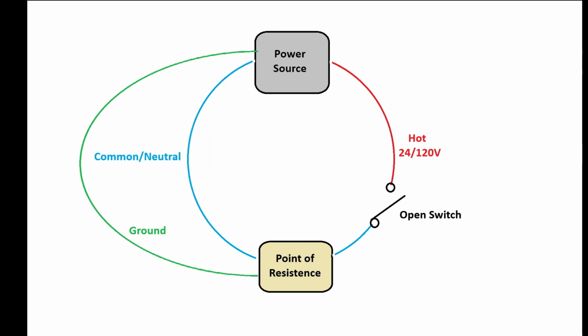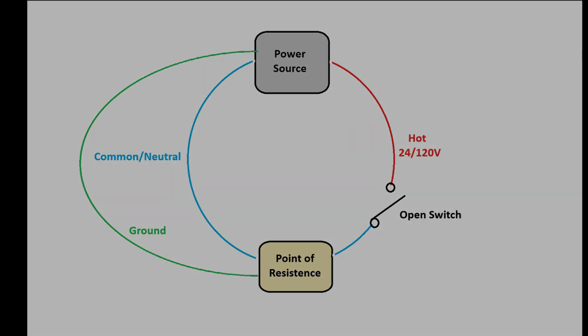Now, sometimes that might be the problem we're actually looking for. But you always have to be aware that ground is a little bit of a risk if you're not absolutely certain it's properly grounded. So using common or neutral is always the better option as a first choice to select as a reference point, and then you can always use ground as a verification.